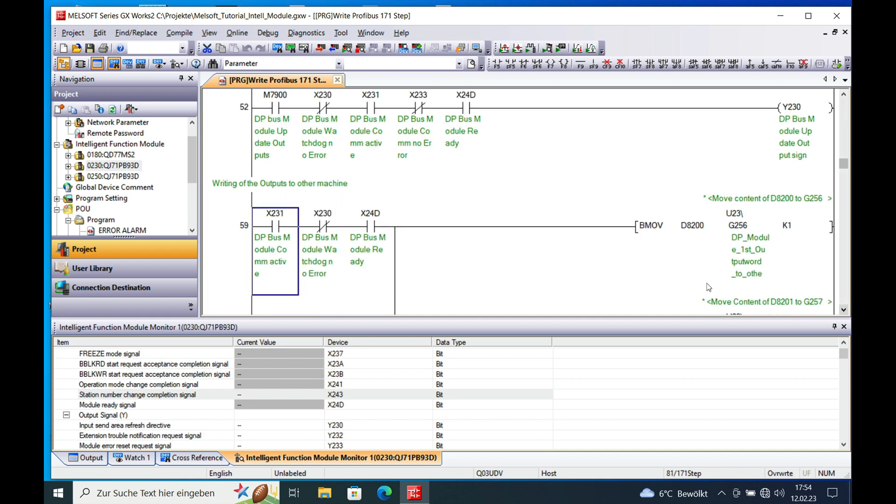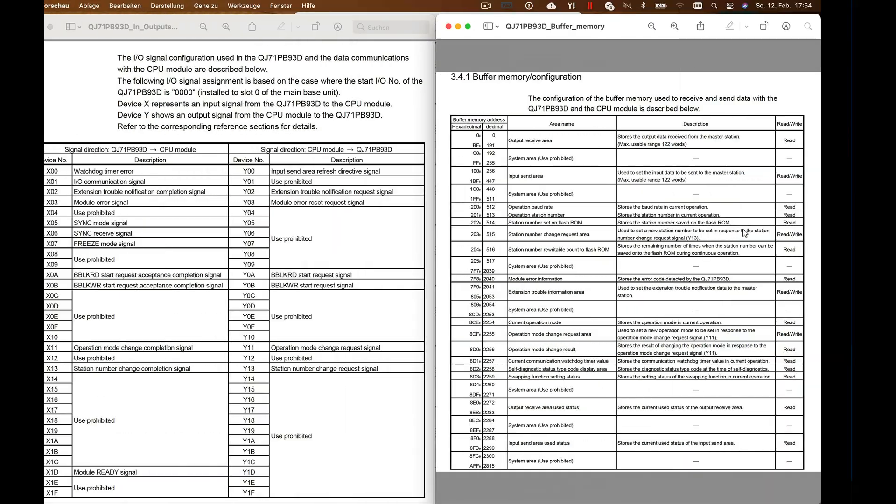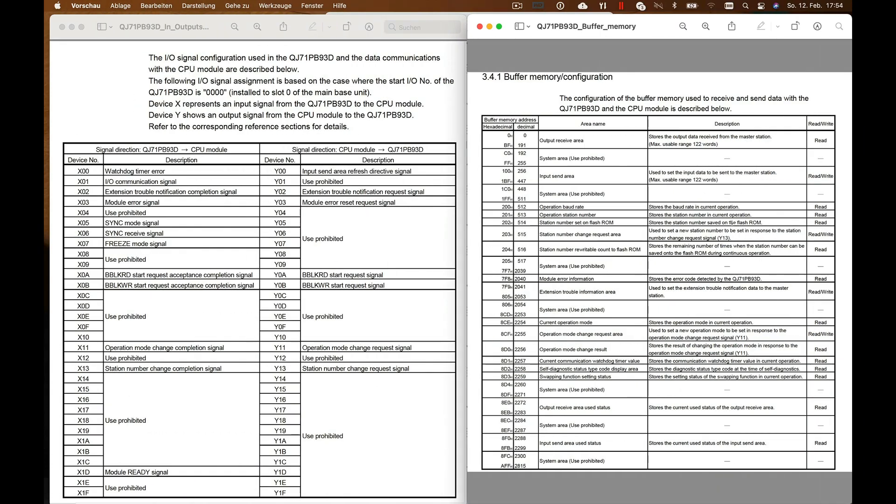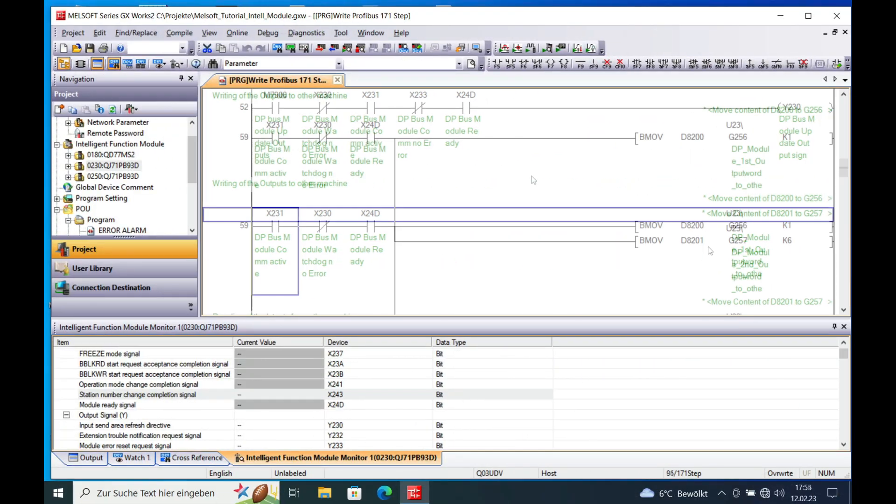And once this is done, then you can go ahead and write your outputs using any register and starting from the U23 which is your address again. And your G256 is your first word writing data to the master. Which you can see right here. Input send area used to set input data to be sent to the master station. That's starting at the buffer memory 256.